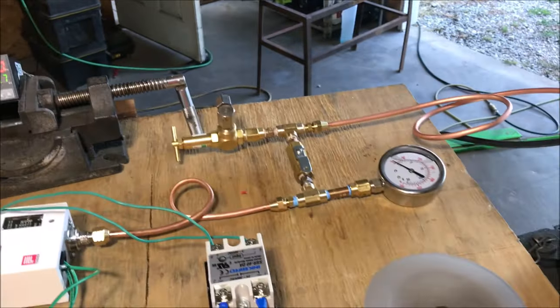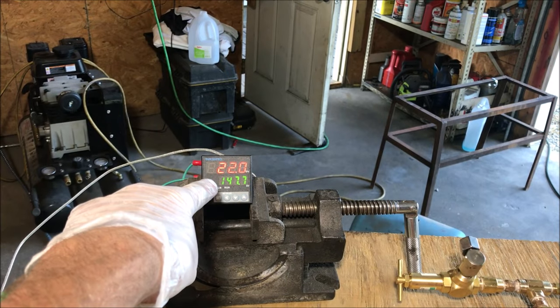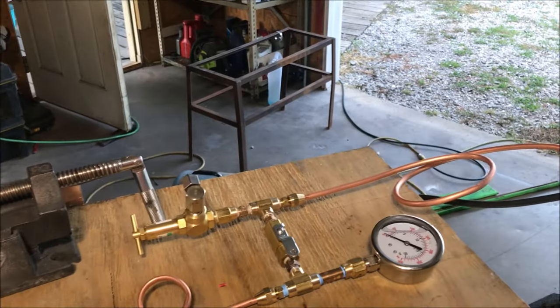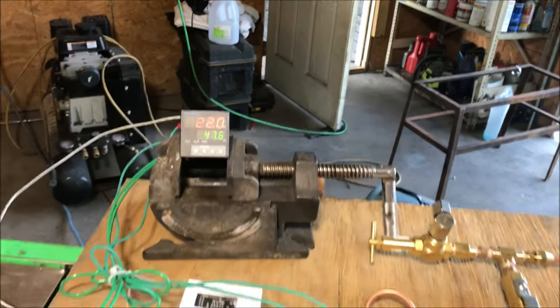The one thing I'm worried about is whether or not this fan shuts off. The first cycle we're going to do is temperature — I'm going to heat up the thermocouple with a small blowtorch. We'll see that when the red temperature indication exceeds the set point — I've set it arbitrarily; actually, let's make it easier and say 47 degrees.